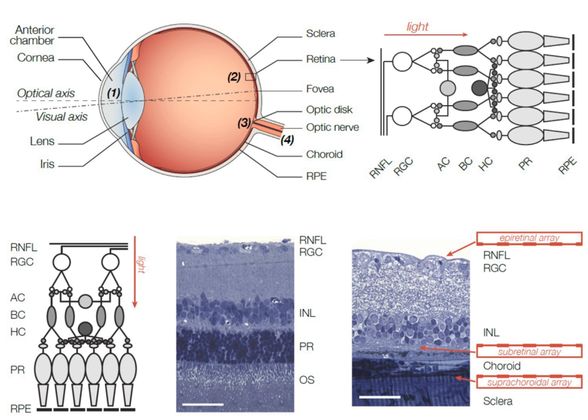The quality of vision expected from a retinal implant is largely based on the maximum spatial resolution of the implant. Current prototypes are capable of providing low-resolution, pixelated images. State-of-the-art retinal implants incorporate 60 to 100 channels, sufficient for basic object discrimination and recognition tasks. However, simulations of the resultant pixelated images assume that all electrodes on the implant are in contact with the desired retinal cell; in reality the expected spatial resolution is lower, as some electrodes may not function optimally.